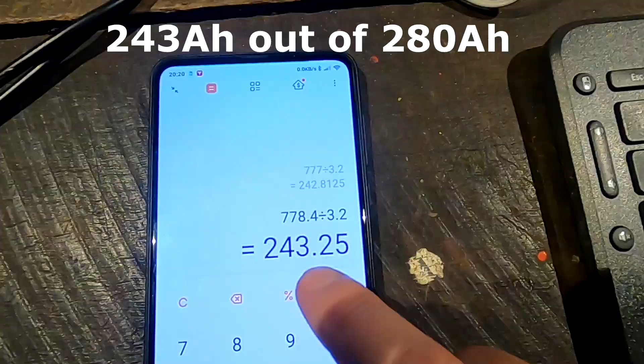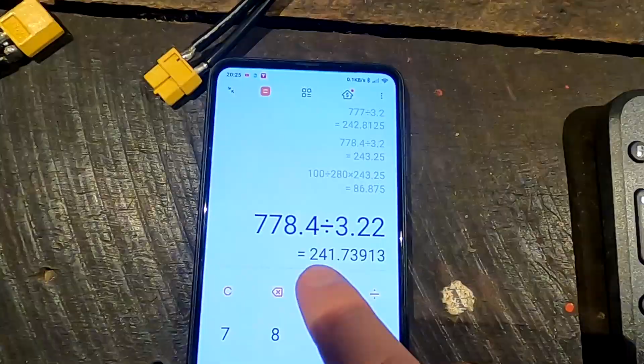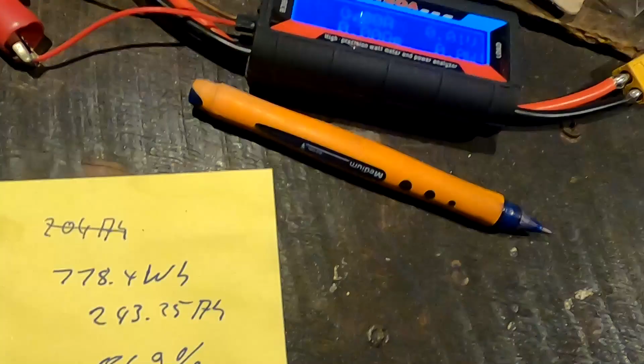Well, the voltage during discharge was between 3.3 and 3.2 volts most of the time. But at the end, if you remember this curve, you can see it's falling off fairly quickly. So if I assume a higher voltage of 3.22 volts, we are only getting 241 ampere hours out of this battery, not 243. So the higher the voltage we assume, the less ampere hours we get out of it, of course.